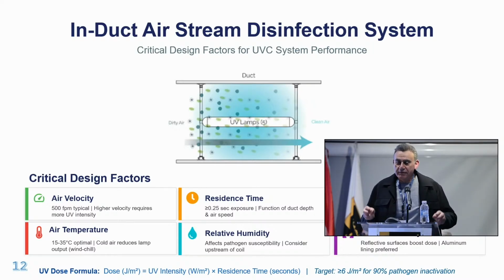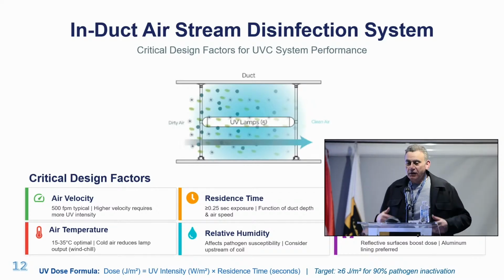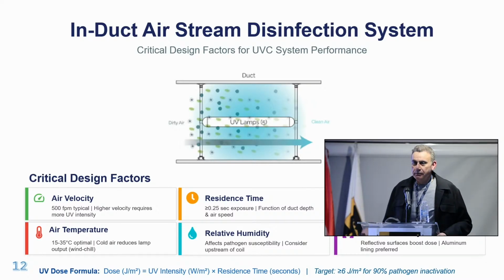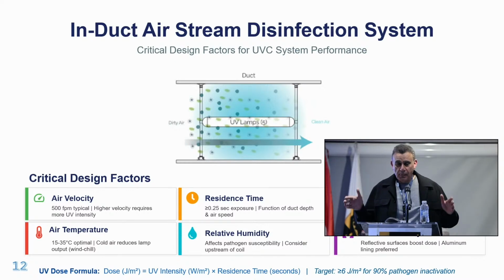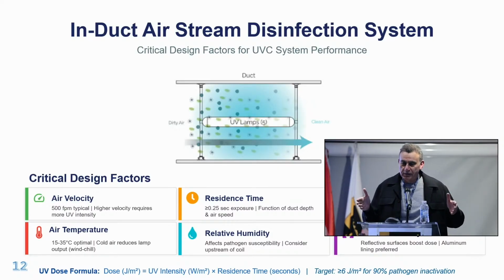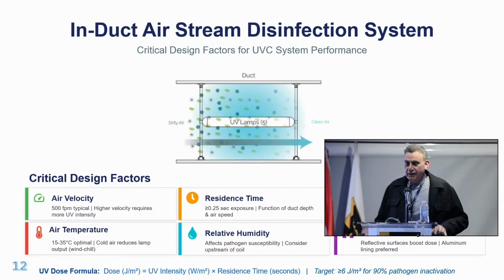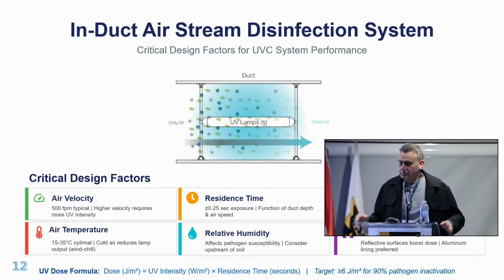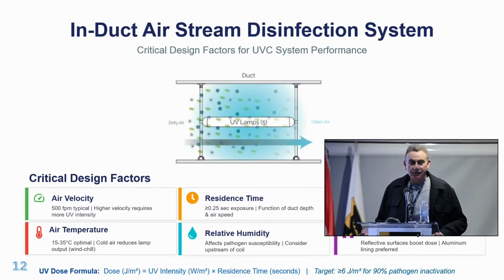The second most important is the velocity, the speed of this air over the bulb. The lower the speed, the more effective the system is, and the less wattage you need. The best speed actually is 2.5 meters per second or 500 feet per minute across a plenum. So you need to make sure you have a plenum that can give you the entire airflow at 2.5 meters per second before you decide to place the lights. If you place these lights in a regular duct where you have 1,500 feet per minute, it's a waste of money. It doesn't do anything. To get disinfected, you need time. You need residence time. It needs to take its time, slowly moving over these lights.